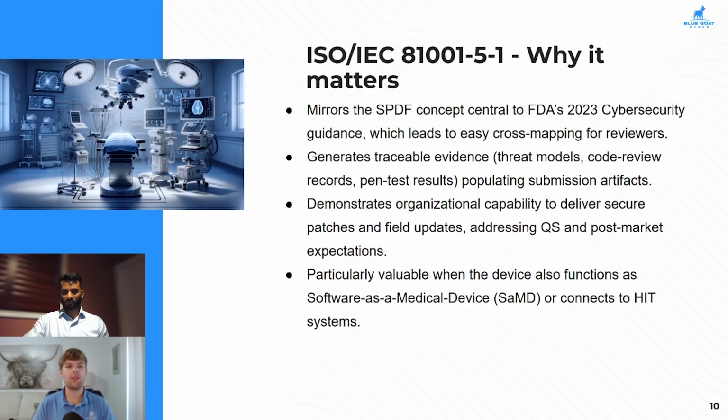They don't want devices to just be a one and done process. While it's still acceptable, if you're going to expect to use a device multiple times over an extended life cycle, the FDA wants to see that you have a way to address risk once it's been fielded. Usually this is going to be through an update process. In worst case scenarios, this can maybe be through a recall procedure. And again, it should be through a scaling level of risk. But having an update procedure in your product is something that the FDA really does like to see.